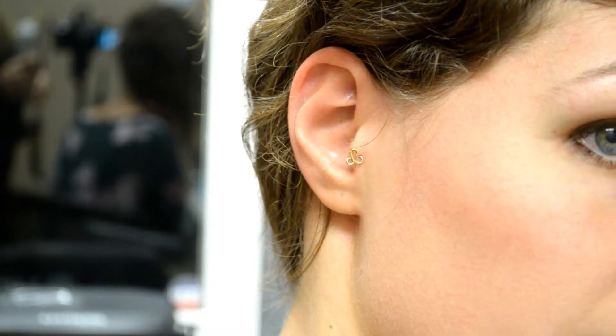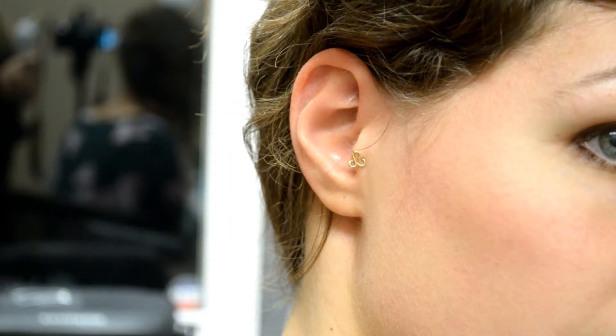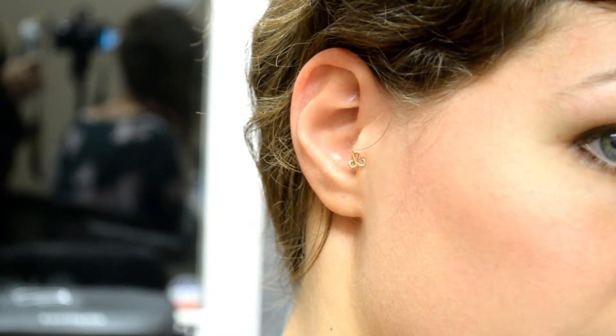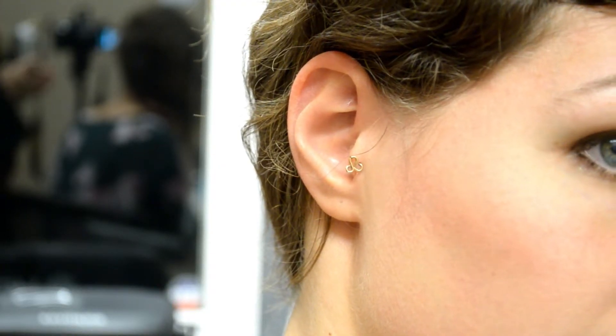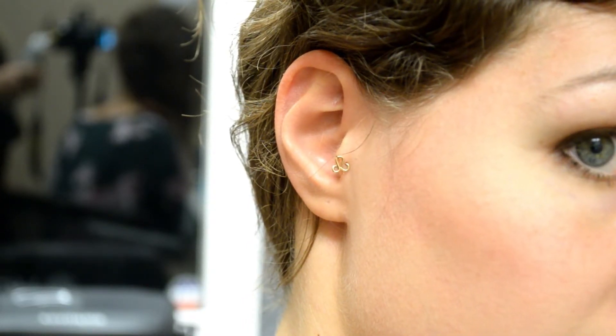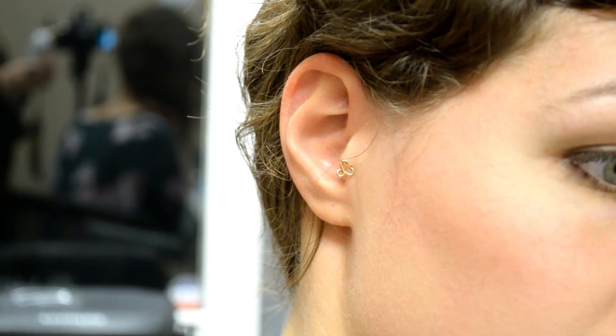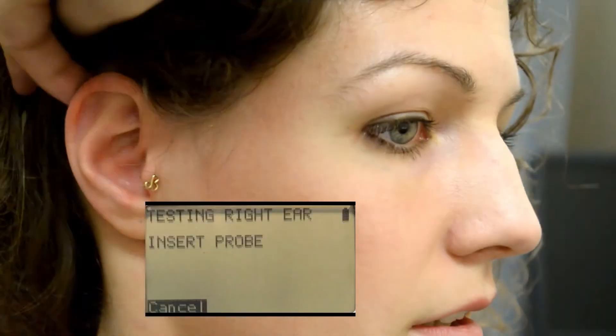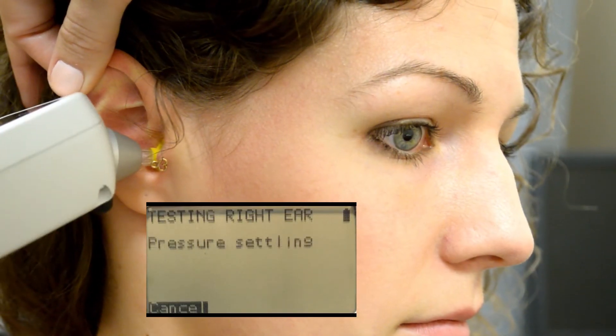Sometimes you'll have different types of issues to consider with the ear. She has a piercing on her tragus, and sometimes that will lead to difficult insertion of either your otoscope or your tympanometer. I'm going to show you how to work around it. After otoscopy, look at the ear canal size, then pull back and you can usually just work your way around it.